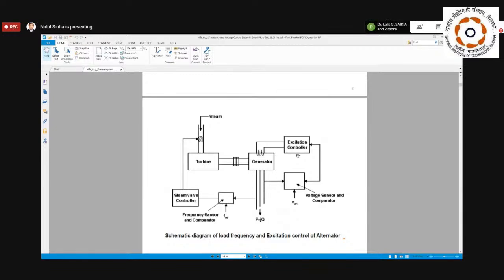reactive power conditions are in the system. Reactive power conditions mean how much is the reactive power demand and how much is the reactive power generation. If there is an imbalance between the reactive power demand and generation, there will be excursions or variations in the voltage, reflected in the voltage variation. The variation of reactive power, whenever there's an imbalance, is reflected mainly in the voltage.